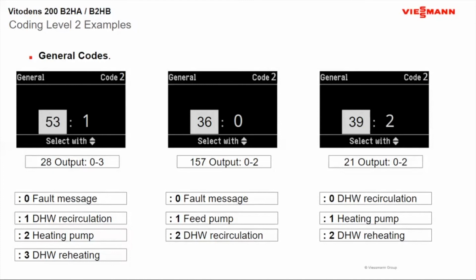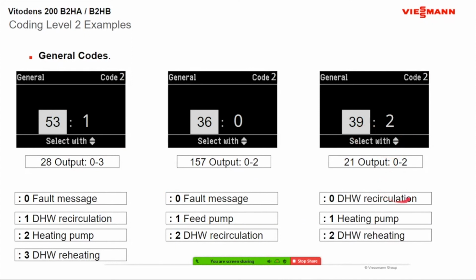Still in your general coding outputs here, at 53 you can go in there and change the outputs of your pumps. 36 as well, that's for your 157 output. The 53 code is going to change your 28 output. And then code 39, if you wanted to go in there without starting the startup wizard again, you can go in there and make the changes to whatever type of pump you want it to be.